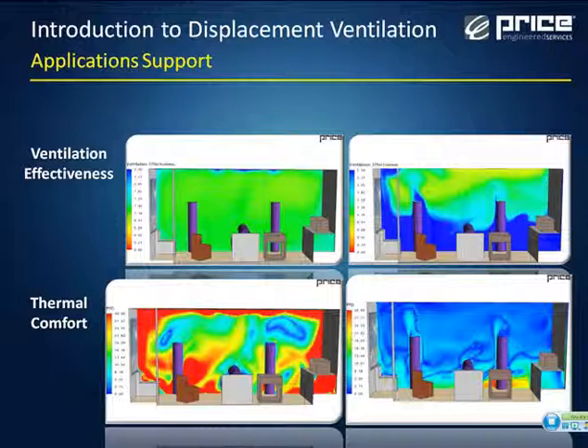If we look at the displacement case, the majority of the room is pretty well in this dark blue zone, which is indicating less than 8% PPD. And the dark blue is actually the 0 zone. So there is a significant portion of the room that's much less than 10% PPD, with the exception of this one zone along the floor, which is right adjacent to the diffuser, so you're going to get some significantly lower temperatures in that zone, which could cause drafts. So that's just a guideline for the placement of displacement diffusers as well.